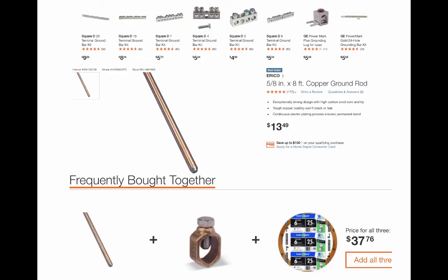So here's some different things. Up top, we have some bonding jumpers. Up top, we have some bus bars that are places where we can bond our neutral to ground and different things like disconnects and things like that. There's a ground rod. A lot of times they are 8 feet long because that's what the NEC says. So there's that ground rod. What you can do is you can take a number 6 wire, see how all these 3 things come together for the low price of $37.76.